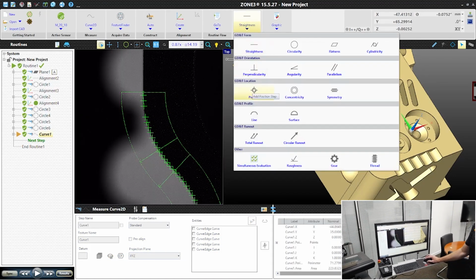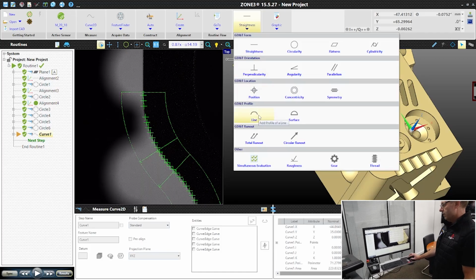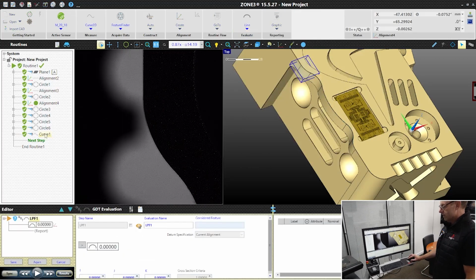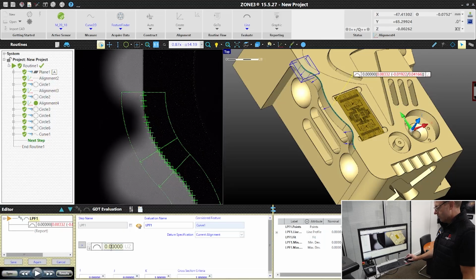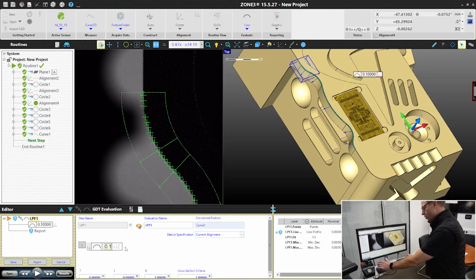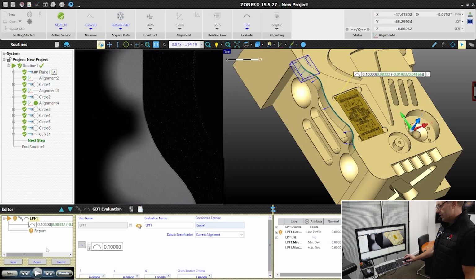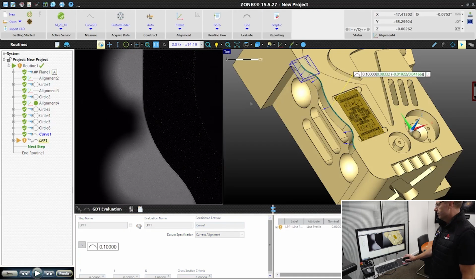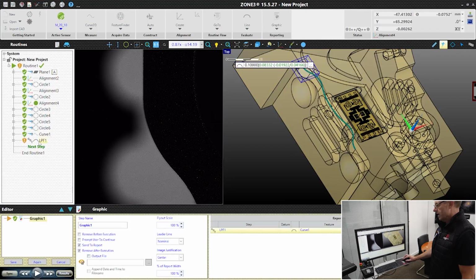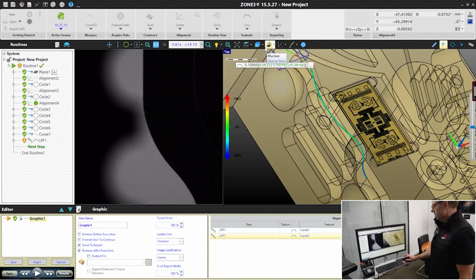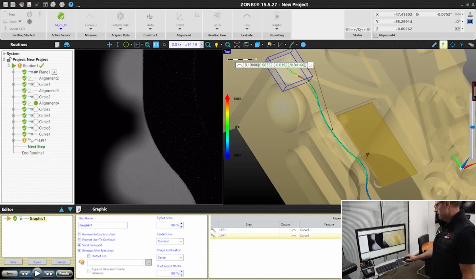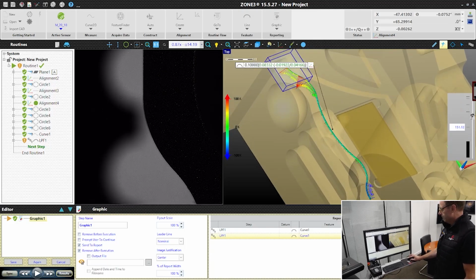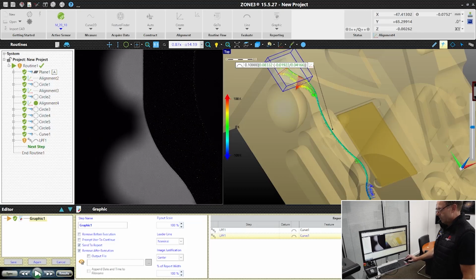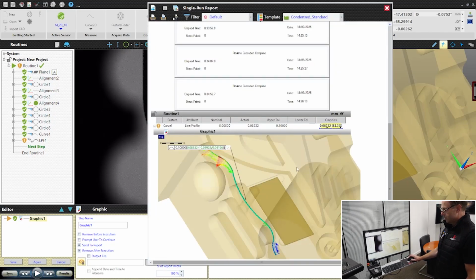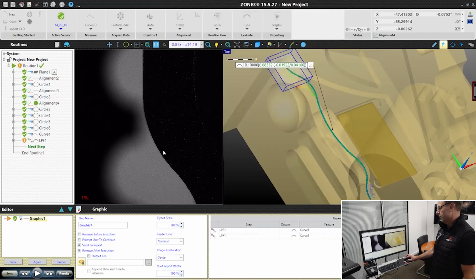We've then got full GD&T in the software. If I want to analyse the curve, I can select the curve, put the tolerance in, just put 0.1 of a millimetre in there, and that is saying that's 100 microns. From that we can also have a nice graphical report. So if I select the curve and then bring that into the view, we can see we have a nice whisker plot on there. If I play that, bring the report up, you can see you can have nice graphics in the report there.